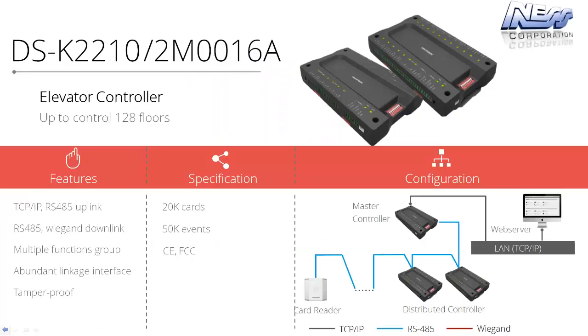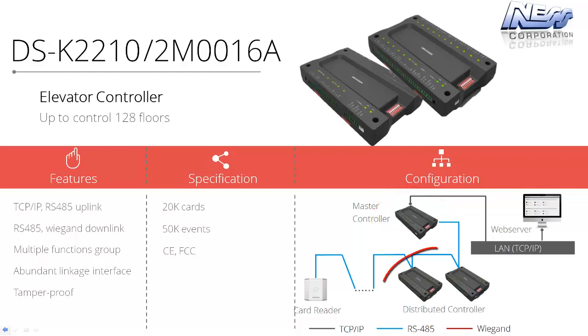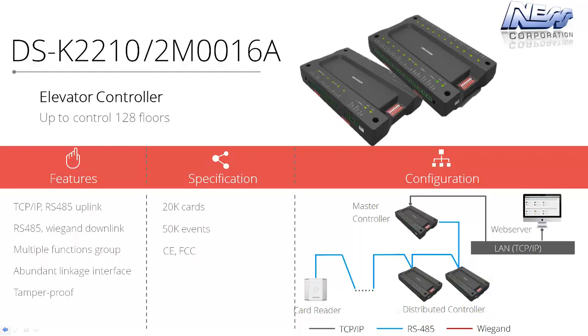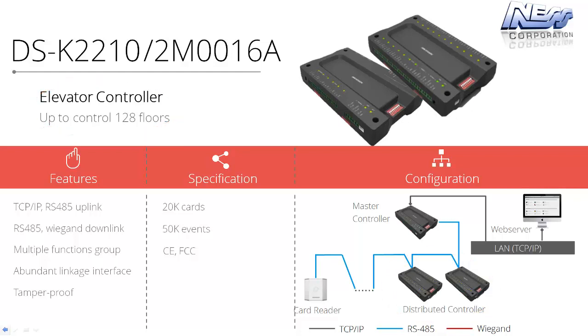The lift interface includes two parts. The first part is the main controller and connected to the main controller on a 485 data bus are the distributed controllers. Each distributed controller has 16 relay outputs, therefore can control 16 floors per distributed controller. We can put up to 8 distributed controllers on the system, therefore we can control up to 128 floors per lift.